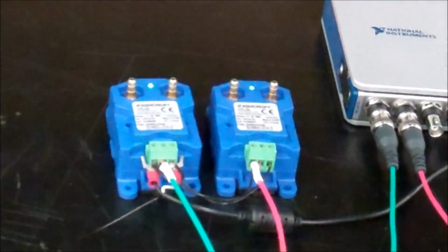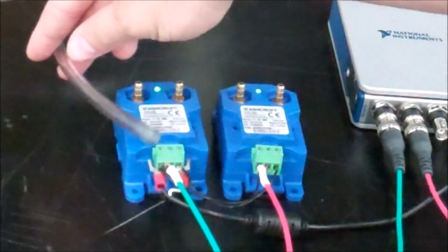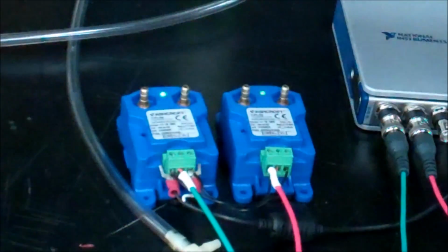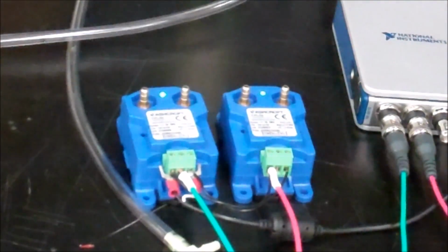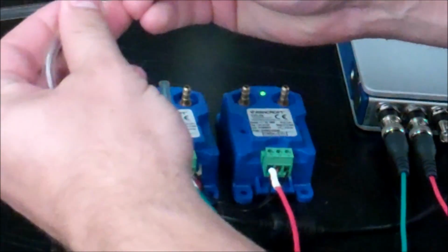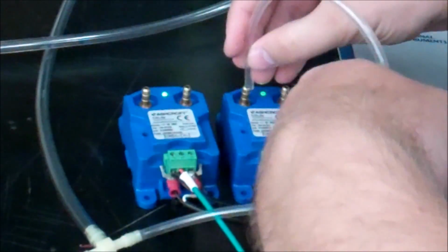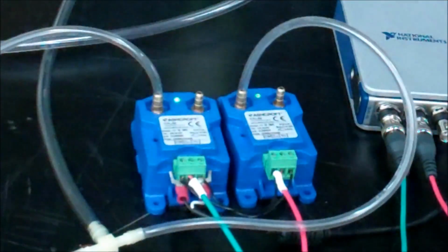By taking this one hose on the manometer, take your T fitting, connect that to the hose coming from the manometer, then you're going to take two bits, the two shorter bits of your core tubing, hook one end of each to the T fitting, then the first time we calibrate it, you're going to connect both to the high port on the pressure transducer, which is the left port, as you can see here on the video.